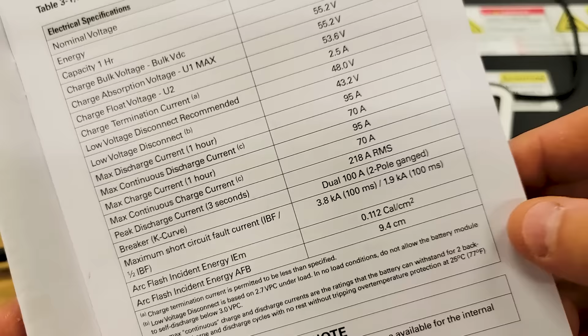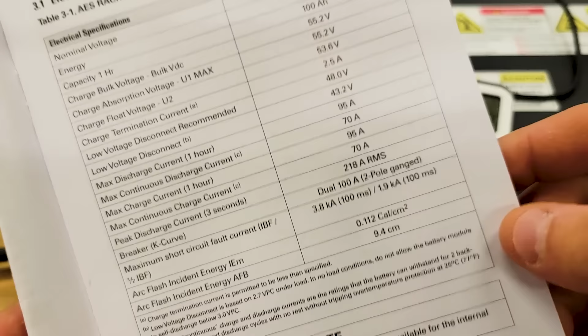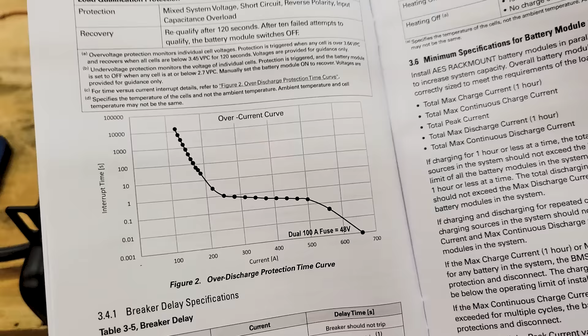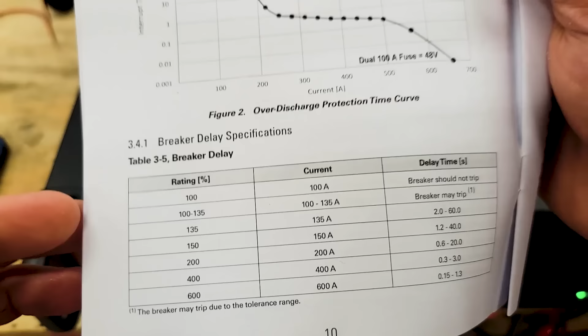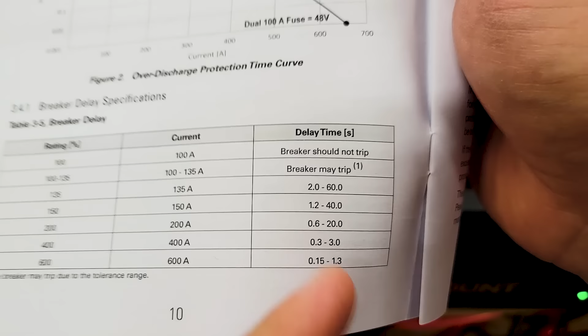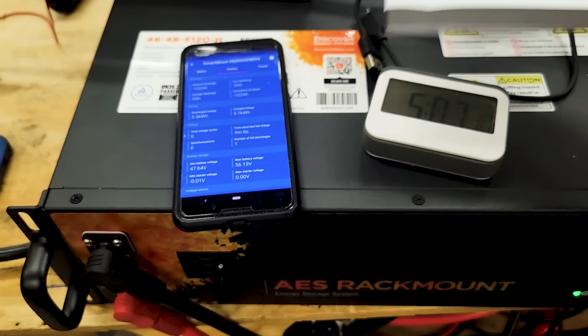At this point, I'd like to do an overload test. It says here peak discharge current is 3 seconds at 218 amps. Now a couple of pages over, we see an overcurrent curve for the breaker. We can see that if we go to 200 amps, the breaker might trip between 0.6 and 20 seconds. Anyway, so let's try discharging it at 200 amps and see if it can handle doing it for a little bit.